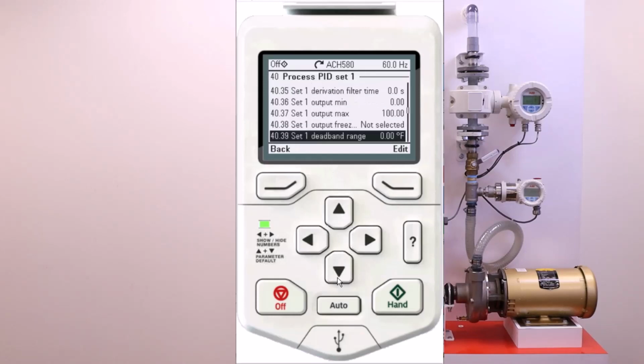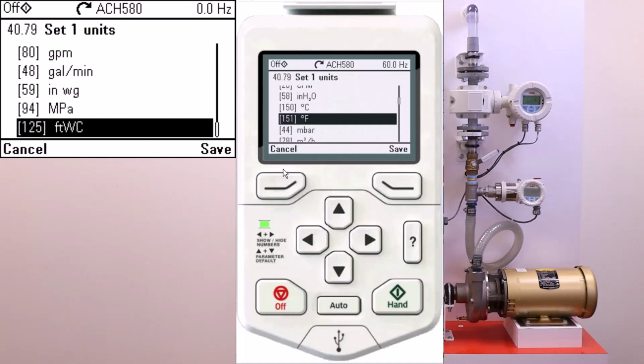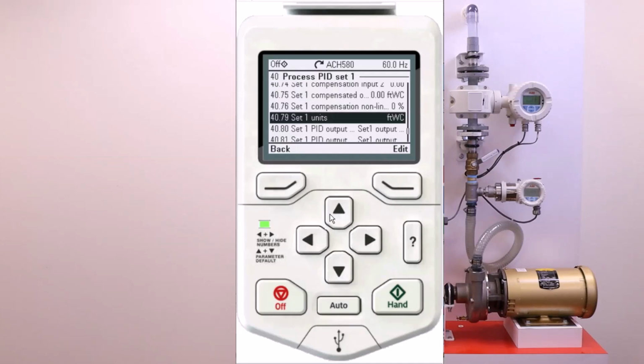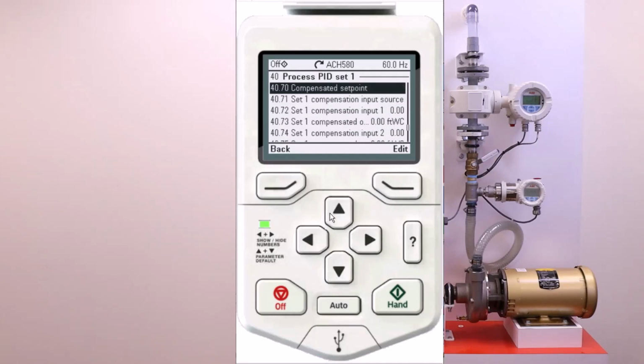All right, let's get our units fixed here. We're still looking at Fahrenheit, so we get down to 79 down here. There's my units right there. I'm going to edit that. And my units are in Fahrenheit. We want to get these units to feet of water column. Inches of water column, just pass that up. Feet of water column, right there, last one. So we can save that. Now when I look at our units on the system, go back to the top, group 40. And there we are. Group 40, feet of water column.